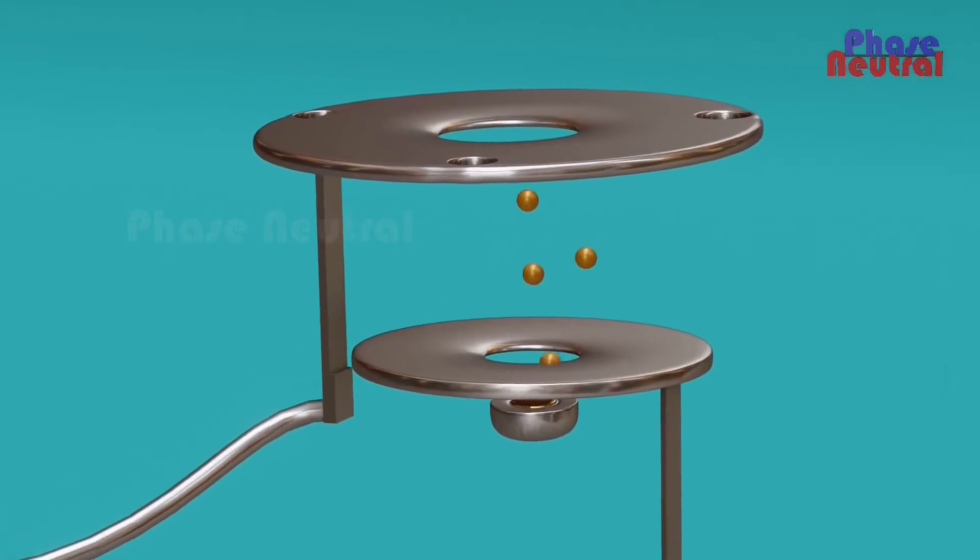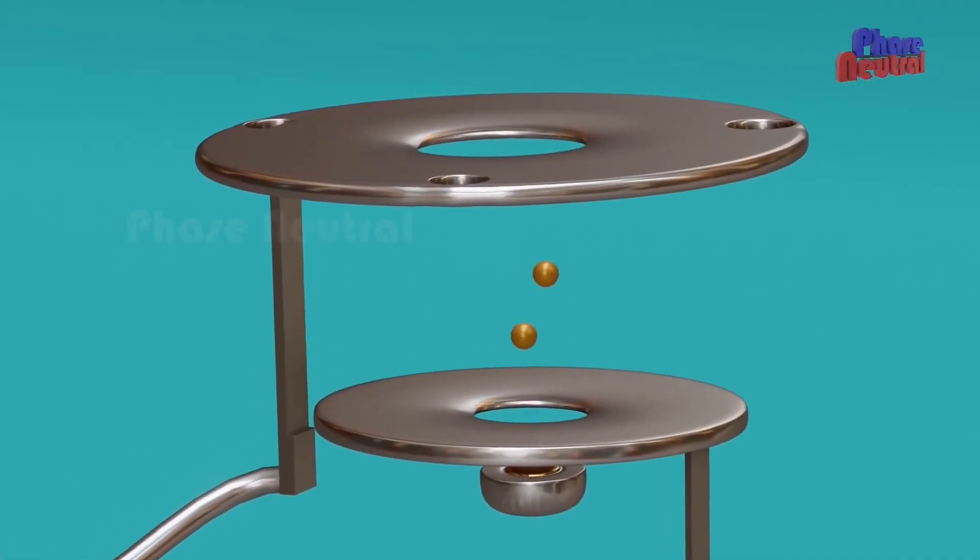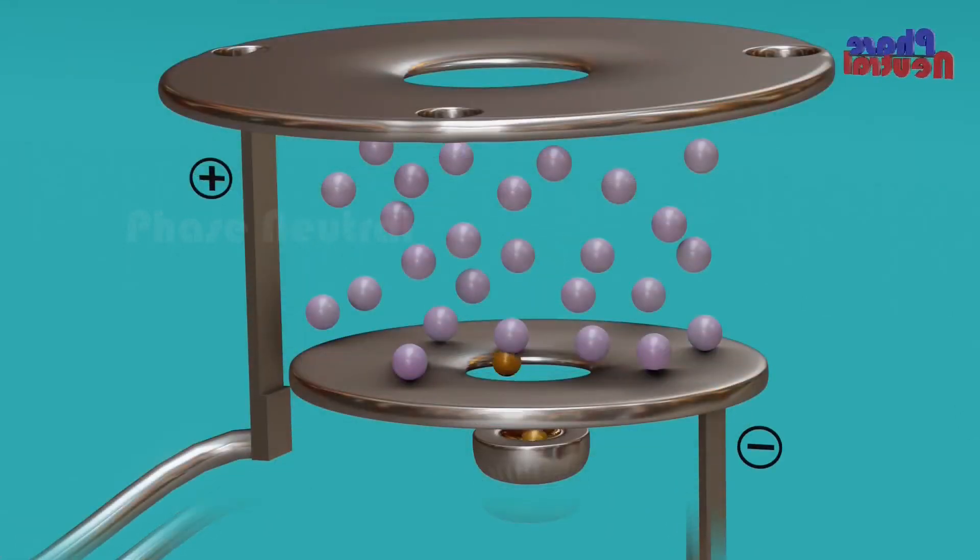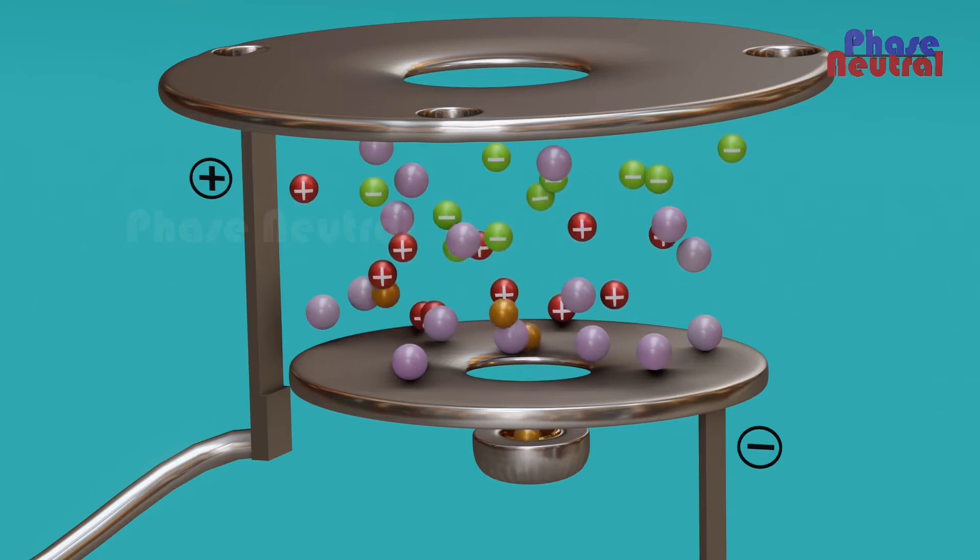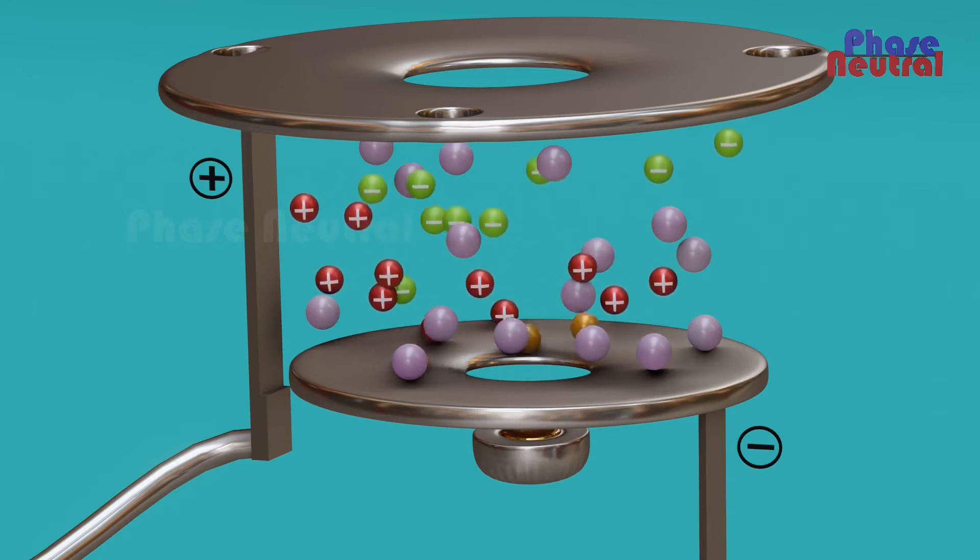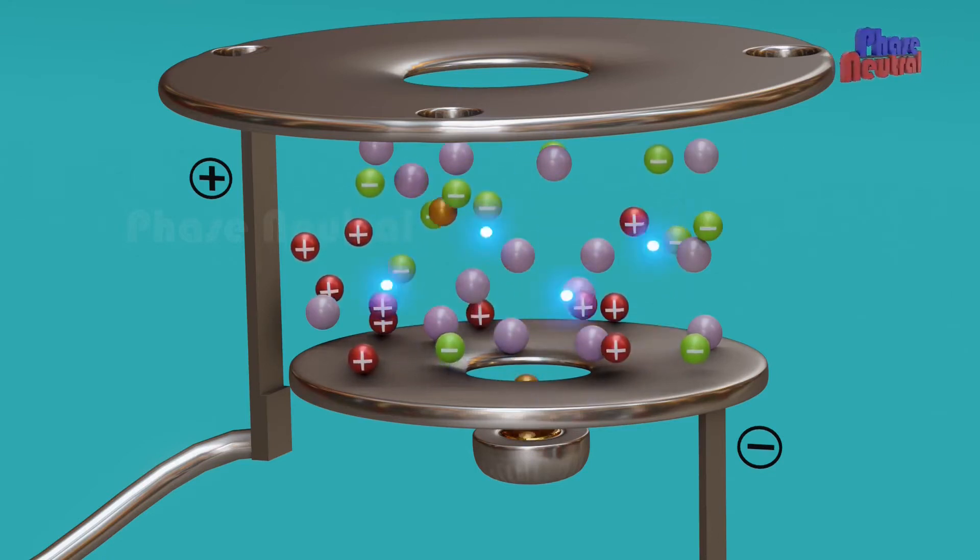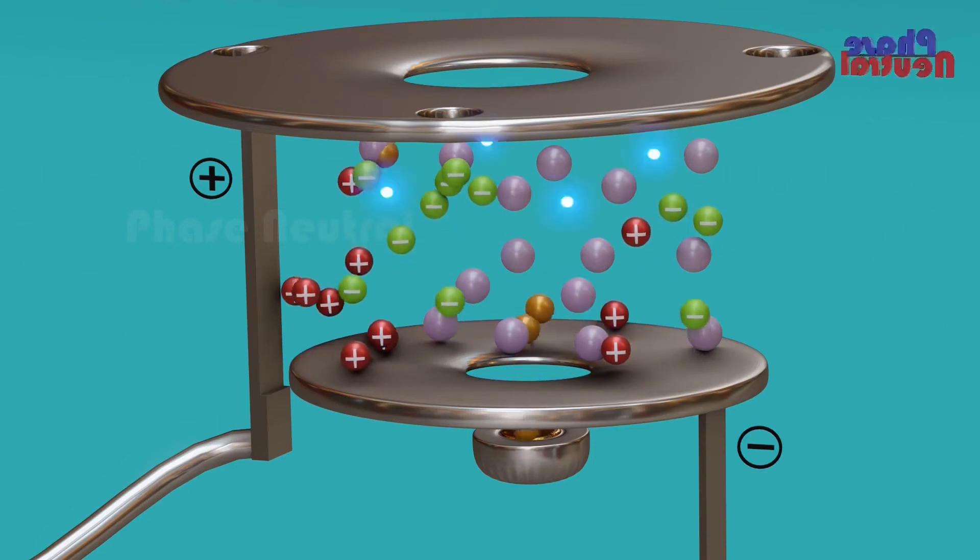Americium-241 constantly releases alpha particles that knock out the electrons from the surrounding atoms in the air, making positively and negatively charged ions. The positively charged ions are attracted to the negative plate, and the negatively charged ions are attracted to the positive plate. This forms a small continuous electric current flow between these plates.